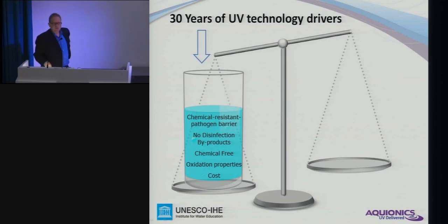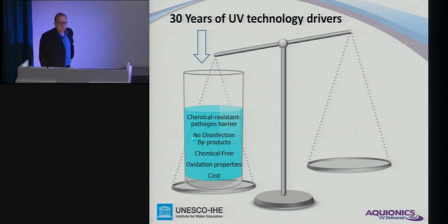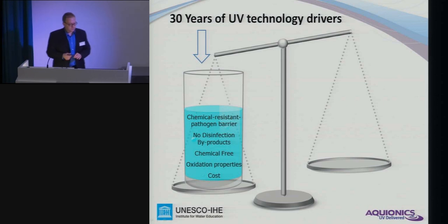Regarding UV disinfection, we pointed out a few things which have driven the UV technology and its development and application. Some drivers include chemical-resistant pathogen barriers. You may have heard about cryptosporidium — water-borne organisms that can survive chlorination and still result in severe illness. Another factor is that since we're not using any chemicals, there are no byproducts formed that could be cancerous. So chemical-free treatment, some oxidation properties, and compared to other solutions, it is also cost-competitive.